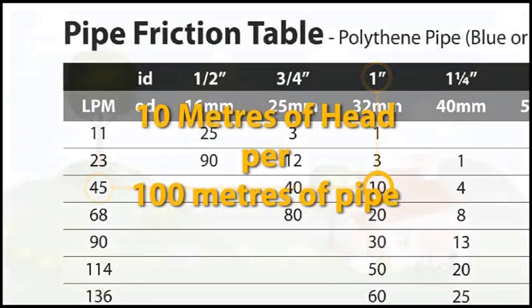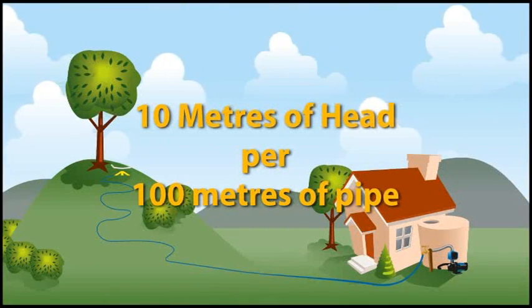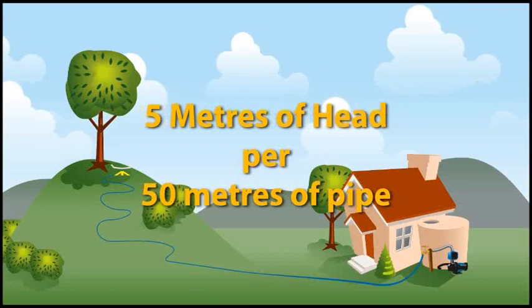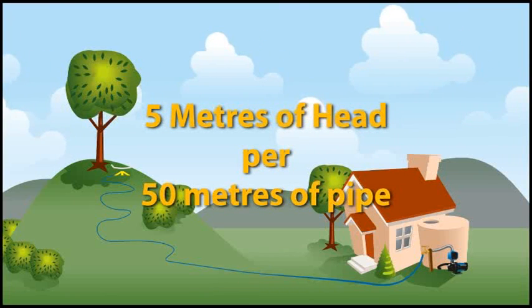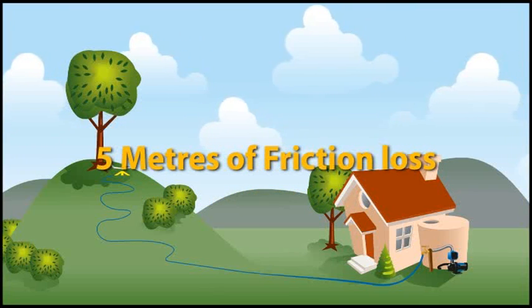However, as we know, in this chart, all values apply to 100 metres of pipe. In Aunty Flo's case, she only requires 50 metres of pipe. Therefore, we must halve the value. Half of 10 is 5. 5 metres is therefore our friction loss.